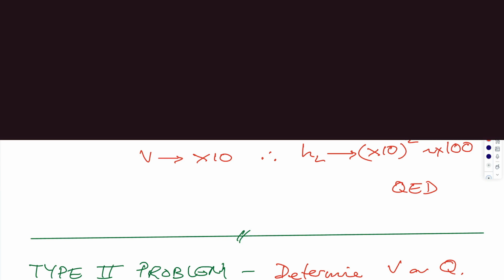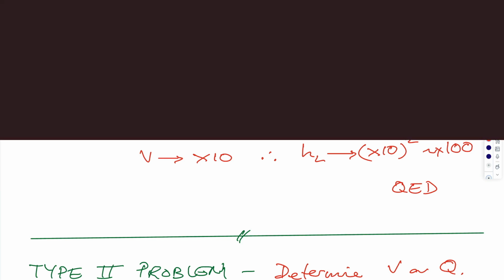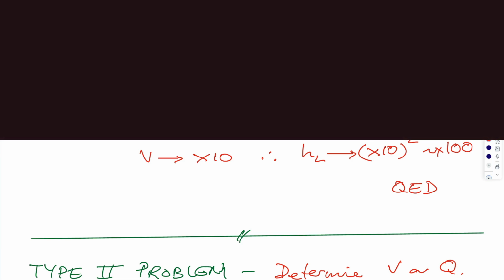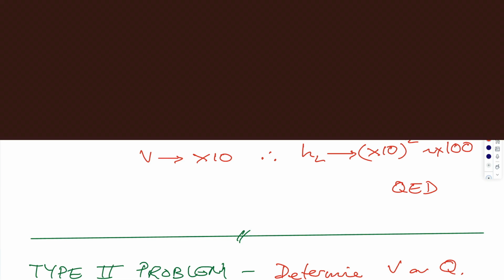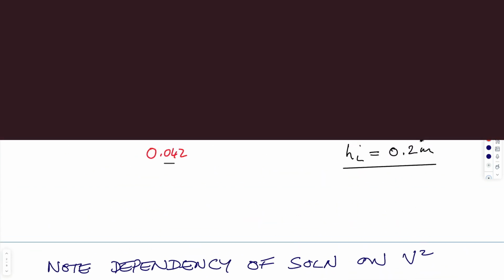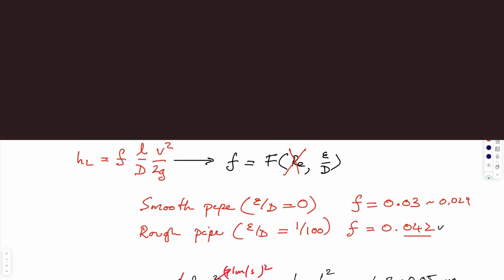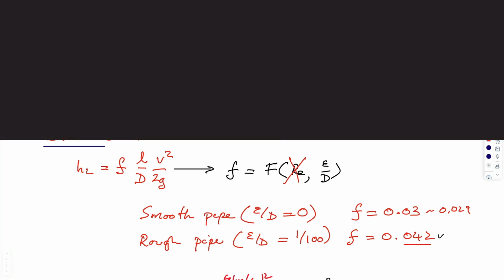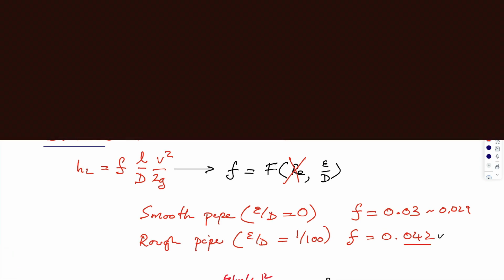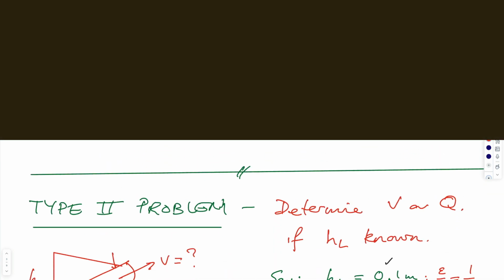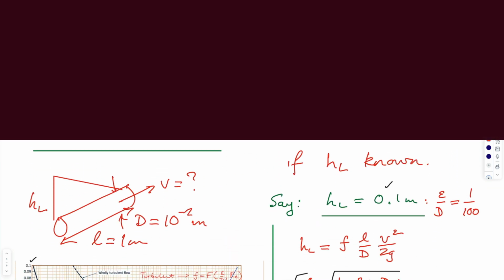The reason is that head loss is a function of v squared. So if you increase velocity from 0.1 to 1 meter a second, you're increasing velocity 10 times, and you'd expect the change in velocity to dominate the head loss. It's roughly correct: this is 200 millimeters, this is 3 millimeters, so it's roughly 2 orders of magnitude different. That might inform what you expect for these things.